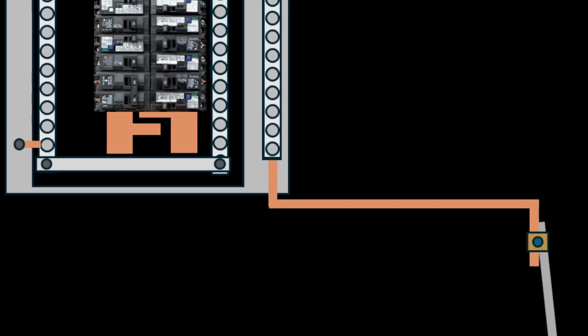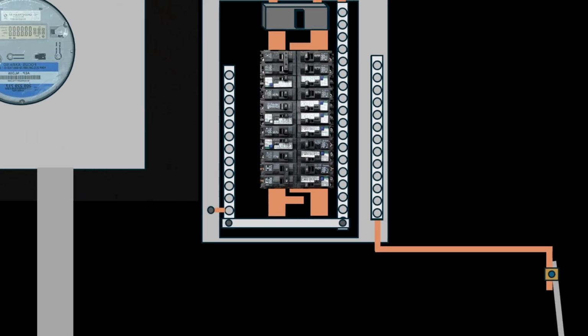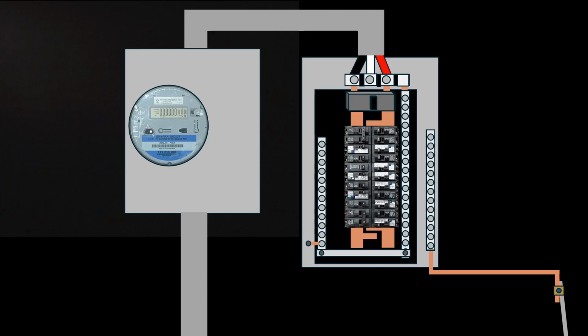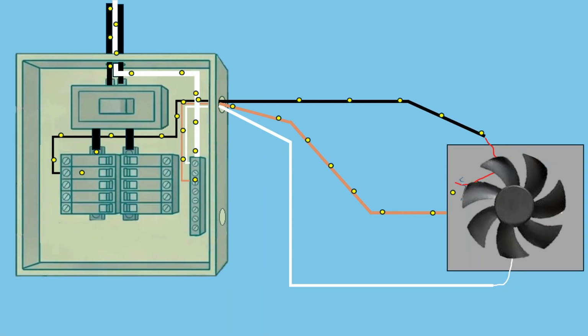Now, this doesn't mean the ground rod is useless. Ground rods are part of what's called the grounding electrode system, and they serve a completely different purpose. They help stabilize voltage levels on the electrical system and provide a path for excess voltage from things like utility surges or indirect lightning. They help protect equipment, not people. Now, this does not mean that breakers never trip during a fault. They do, just not through the ground rod. In a separate video, I show exactly what path fault current actually takes and why that causes the breaker to trip almost instantly. So the key takeaway is this.